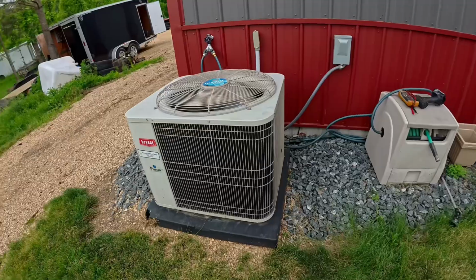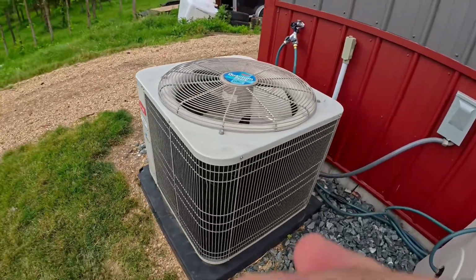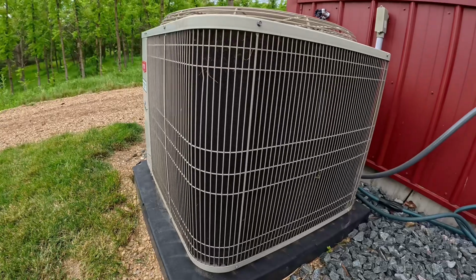So now we're back outside, and we're going to show you a few things to look for on the outdoor unit on a normal basis. Anytime you're walking around the yard, cutting the grass, things like that, if the AC is running, here are a few things to check. First and foremost is the cleanliness of the outdoor coil.